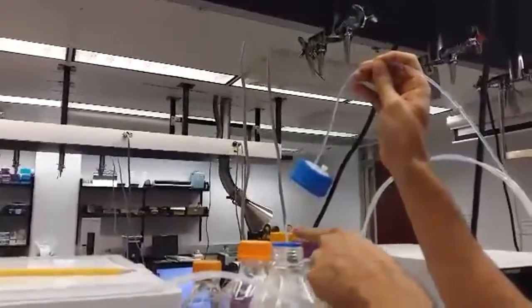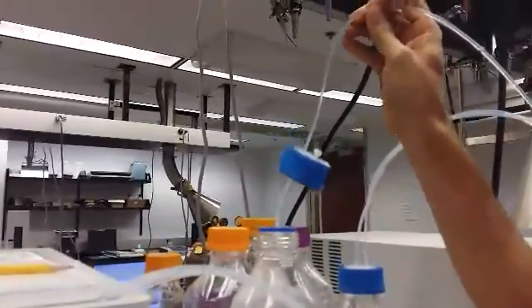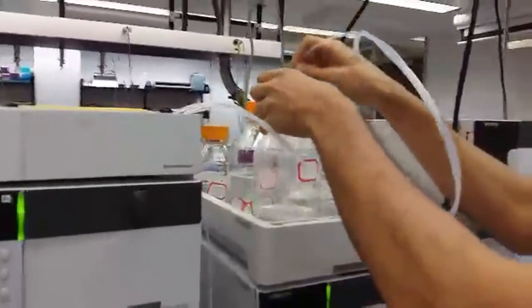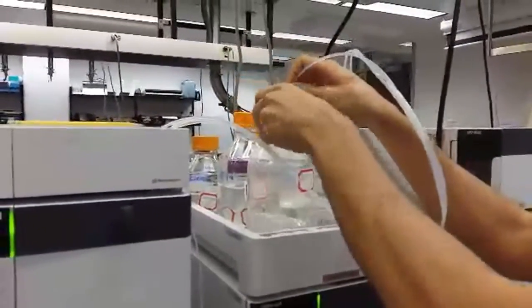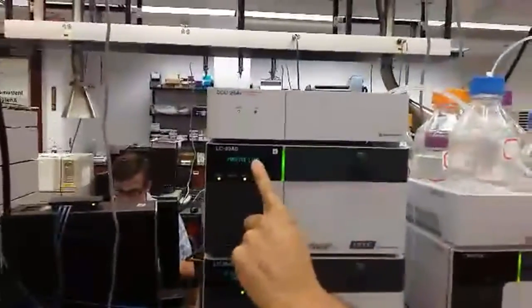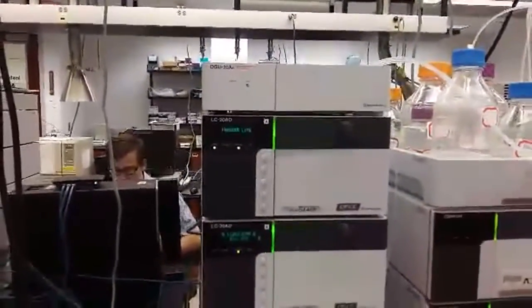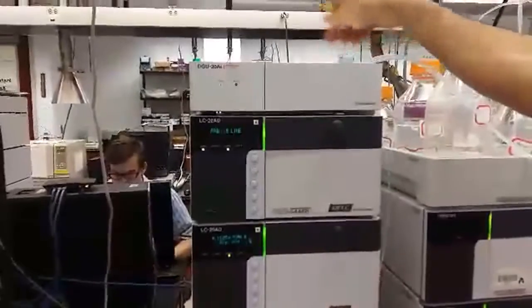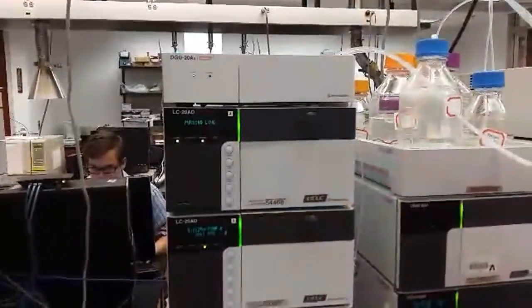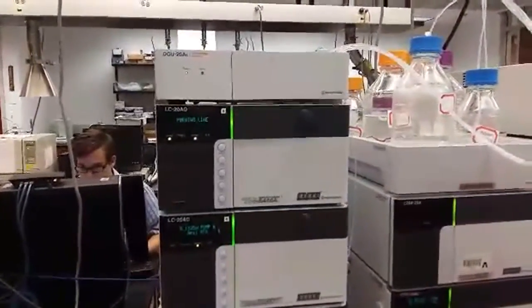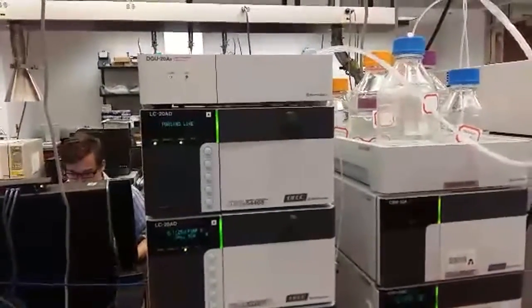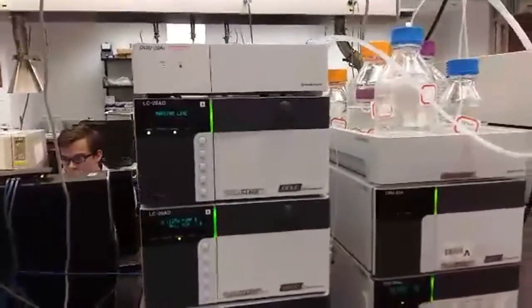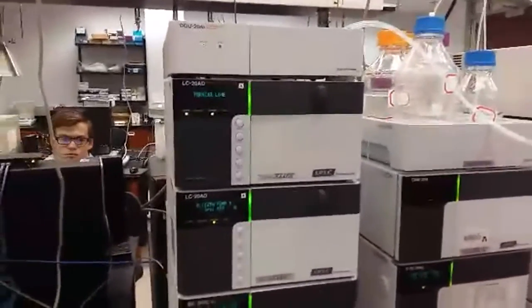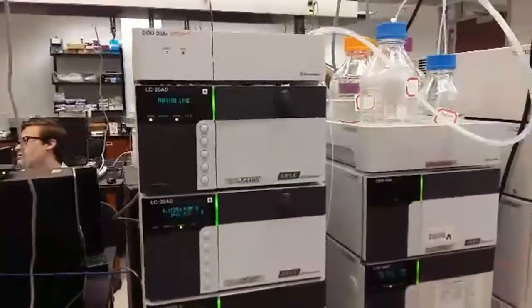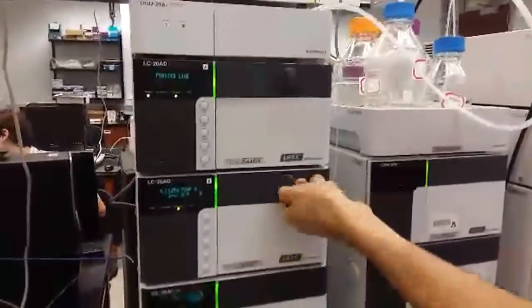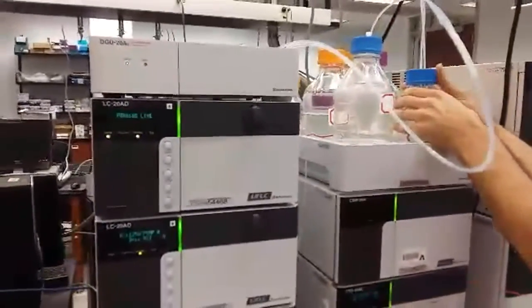You see the bubble? Now we are fine. We will put this tube back to the reservoir and wait for the "purging line" message to disappear and the pump goes back to the standard state it was. We do the same thing for the methanol reservoir, meanwhile.